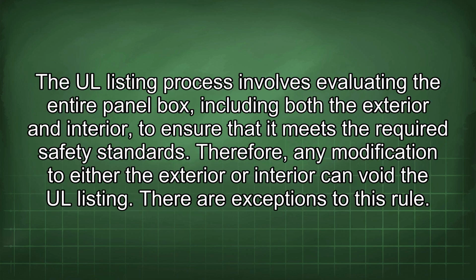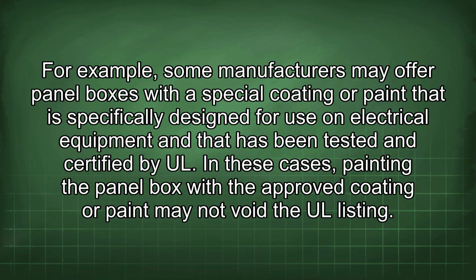The UL listing process involves evaluating the entire panel box, including both the exterior and interior, to ensure that it meets the required safety standards. Therefore, any modification to either the exterior or interior can void the UL listing. There are exceptions to this rule. For example, some manufacturers may offer panel boxes with a special coating or paint that is specifically designed for use on electrical equipment and that has been tested and certified by UL. In these cases, painting the panel box with the approved coating or paint may not void the UL listing.